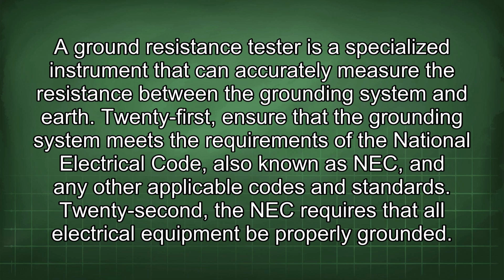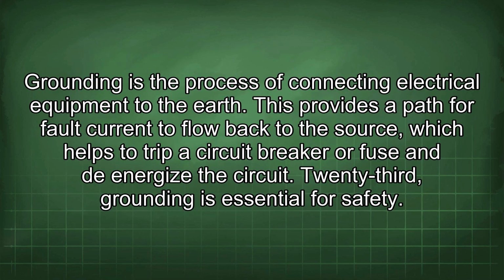21st, ensure that the grounding system meets the requirements of the National Electrical Code, also known as NEC, and any other applicable codes and standards. 22nd, the NEC requires that all electrical equipment be properly grounded. Grounding is the process of connecting electrical equipment to the earth. This provides a path for fault current to flow back to the source, which helps to trip a circuit breaker or fuse and to de-energize the circuit.